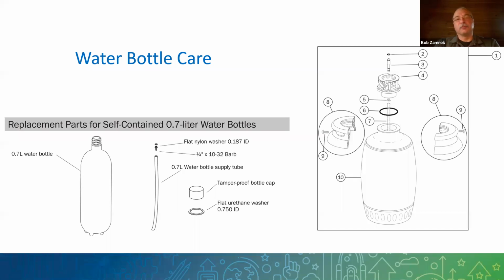Two things can go wrong: the urethane washer needs replacing, or the bottle has problems with its threads. Most bottles are plastic, and we see that a lot. I don't know a technician who doesn't carry at least an extra 0.7 and a 2-liter bottle on their truck, because we're replacing them constantly since they leak. It's more often the threads than the washers or O-rings, because you're constantly screwing and unscrewing them all day to fill with water.